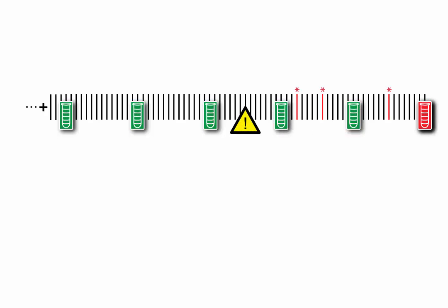In this example, the first two QC events subsequent to the out-of-control condition failed to detect it, but the third QC event gave a QC rule rejection, denoted by the red test tube. During the time that the test system was out of control, 3 patient results had measurement errors that exceeded the quality requirement, denoted by the red asterisks.